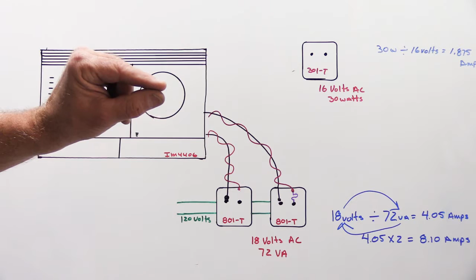Well, a 301T also has a thermal limiter. If the 301T were to be overloaded, and transformers get hot when they are overloaded, the thermal limiter does the same thing as the switch in your old-school thermostat. It will expand and break the connection, and it shuts the transformer off completely until it cools down, and then it closes and the transformer comes back on again. So it is a safety device, but it's more like a self-resetting circuit breaker than a fuse, because if there's a fault it'll shut off by opening, and when it cools down or the fault's been corrected, it'll close and the transformer works again.